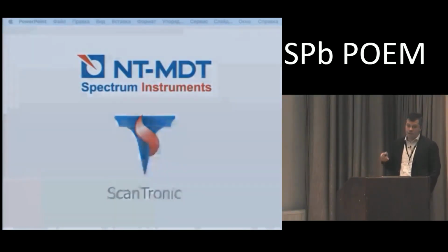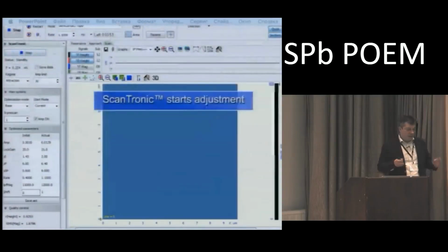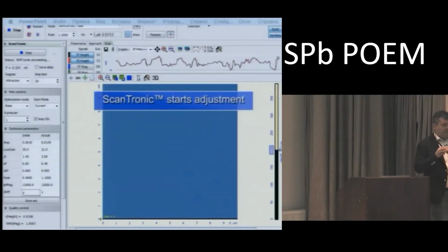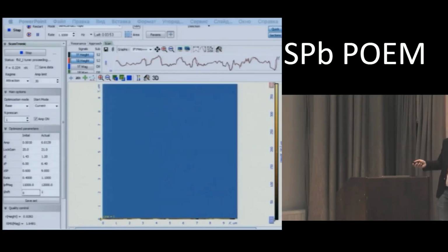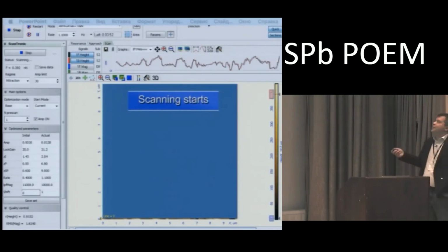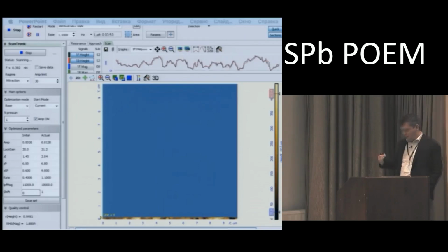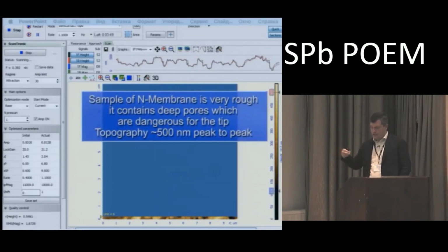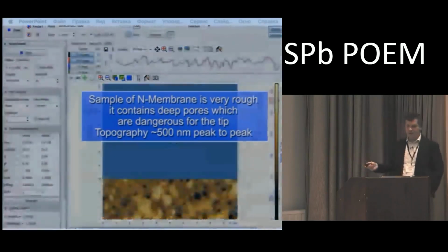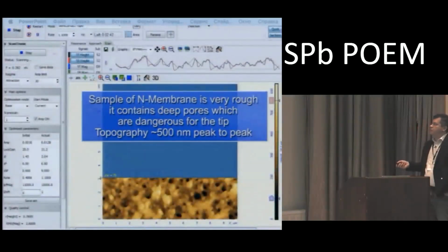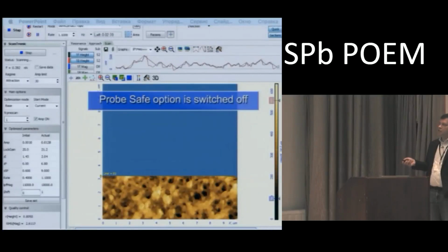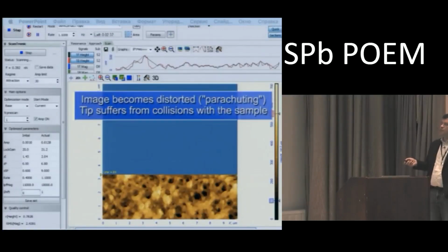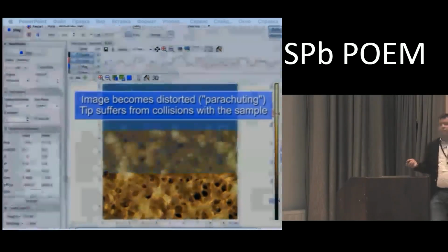And the second point, what I was saying about the correlation between the scan speed and the topography roughness, if we are able to change the scan velocity during the scanning. So if we have the higher derivative of the topography, we can decrease the speed. And if we have a more flat part of the topography, we can increase the speed again. And this is the N-membrane where the scanning parameters are automatically adjusted, and the scan speed is very dependent on if topography is rough or not.